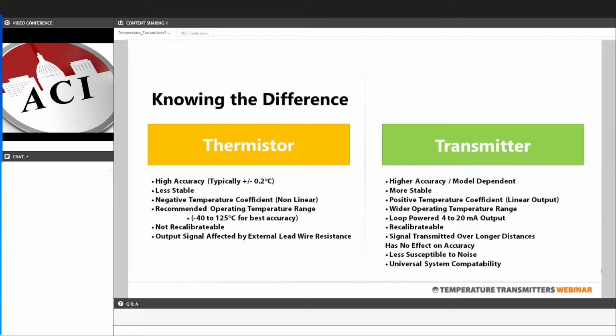That's not to say that thermistors are less accurate or less stable, but because a thermistor has a nonlinear resistance curve at the high ends and low ends of the temperature ranges, specifically if you get below minus 40 degrees C or above 125 degrees C, you're not going to get as stable or as accurate an output as you would with a current transmitter. As such, the temp transmitters offer a wider operating temperature range.